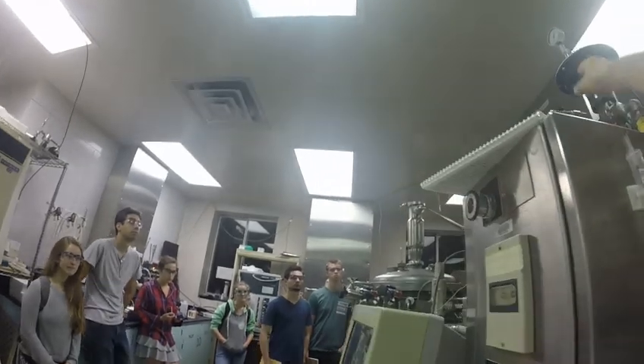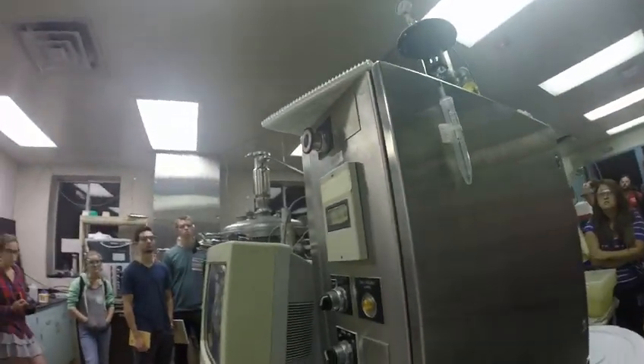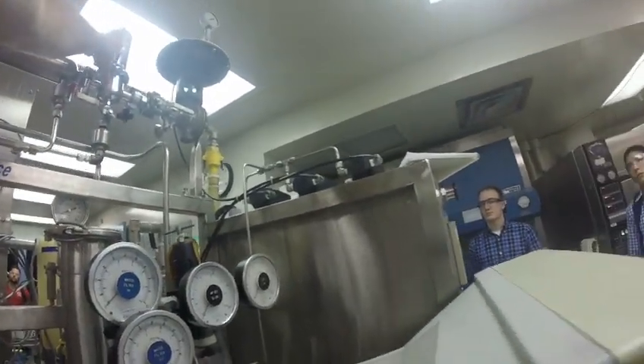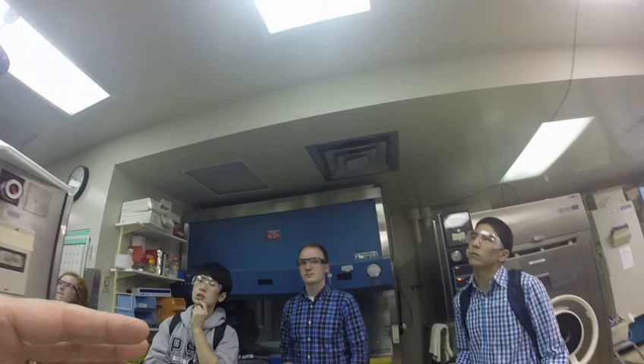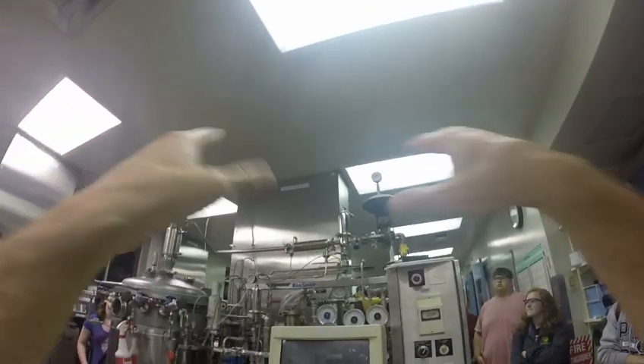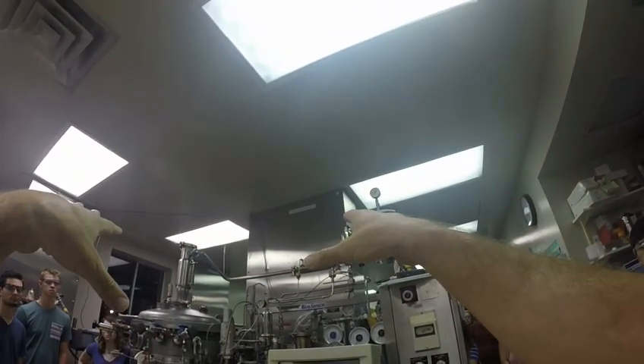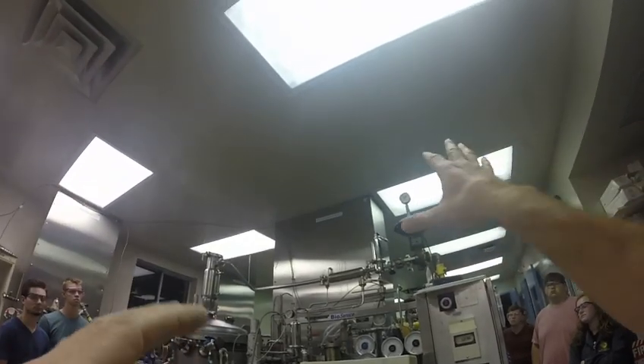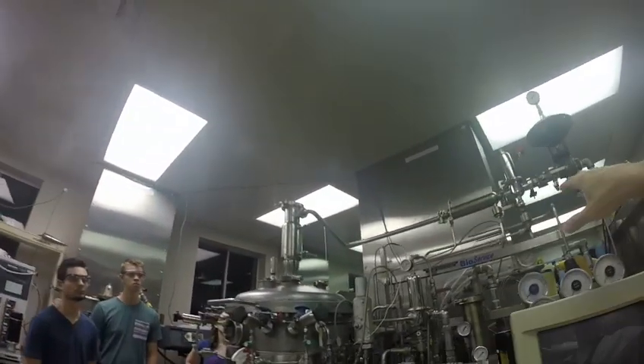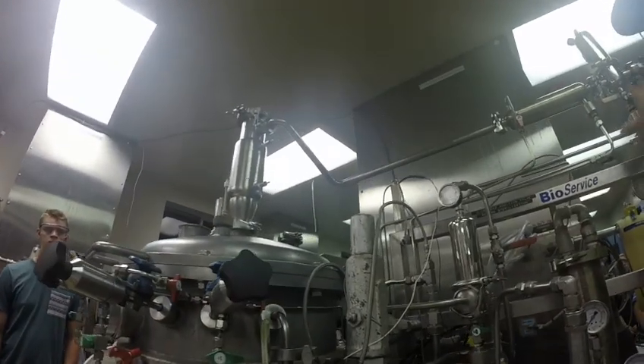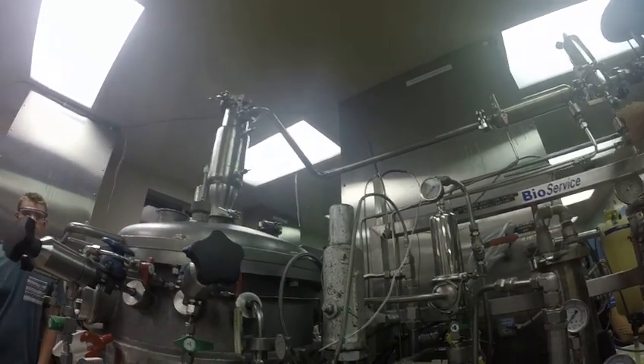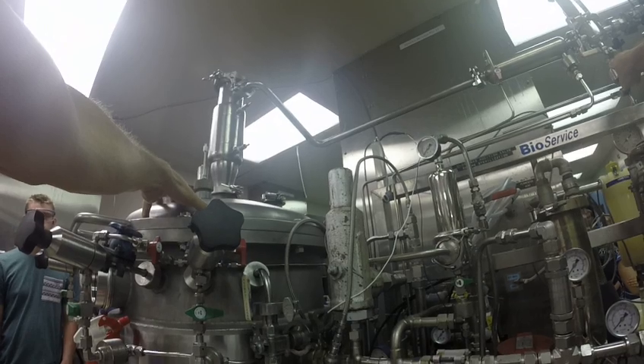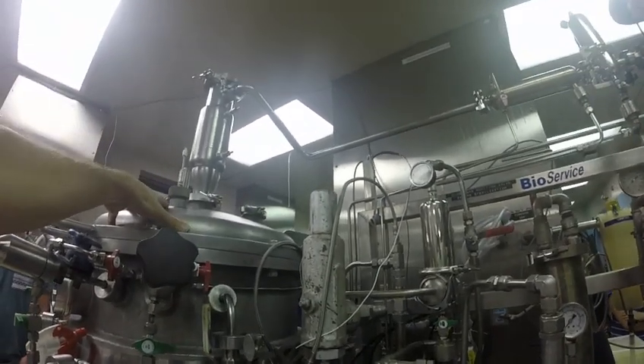As we make our way back, it turns out that little unit there is actually your microbial sterilization filter. Inside there will be like a 0.2 micron filter that will keep anything from escaping the reactor. If you look at it closely, we'll talk a little more about sterility, but that filter can actually be sterilized using the steam that's used to sterilize this. That's what's going on there.